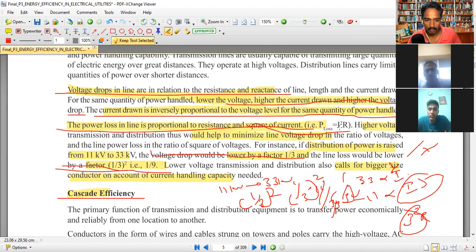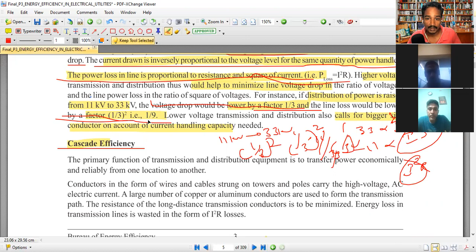And these are the factors they are always asking, every time, one mark. Suppose the distribution level changes from 11 kV to 33 kV, how much voltage loss can we reduce? So 1 by 3 times the voltage losses. And power losses are (1 by 3) whole square.